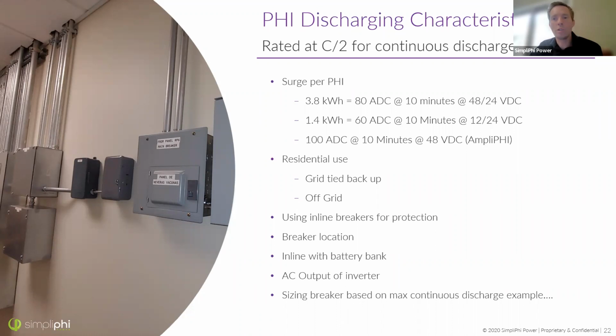5 batteries would just be one too short, right? 5 times 1.9, we'd be a little bit under. We'd be at 9.5 kilowatts of power coming out of the battery bank, so you would need 6. So that's an example. We can go through more if you'd like in the Q&A.